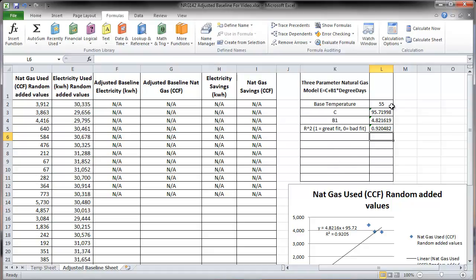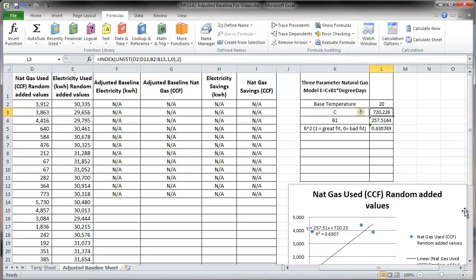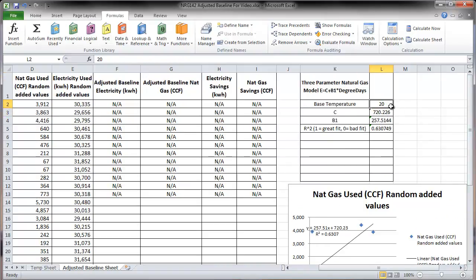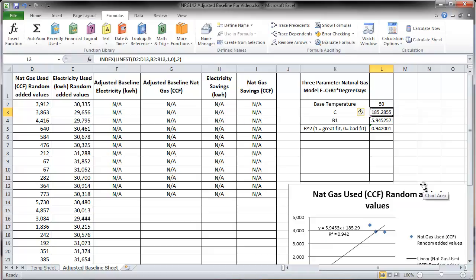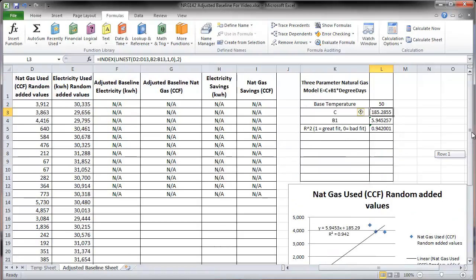Note that if you change the base temperature, the R-squared can go up or down. For example, setting it to 50 improves the fit slightly, while 20 degrades it significantly — and you can see this reflected in the graph because the base temperature affects the heating degree days calculation. You can adjust the base temperature to get better and better fits; if R-squared is very low, try changing the base temperature.